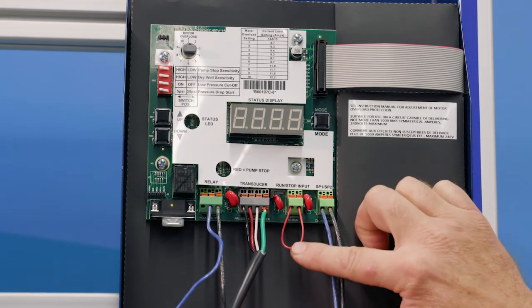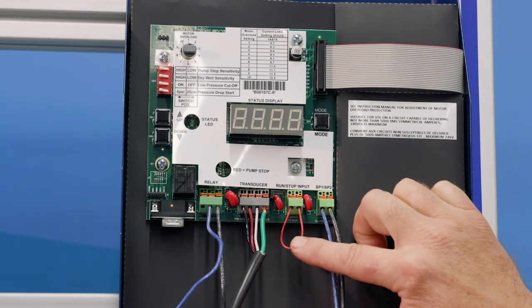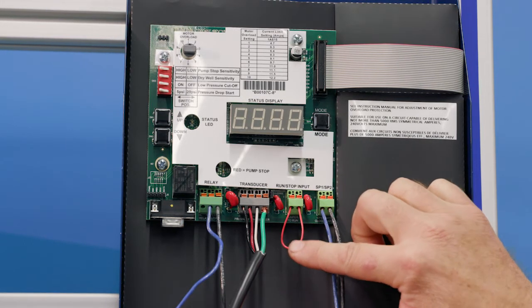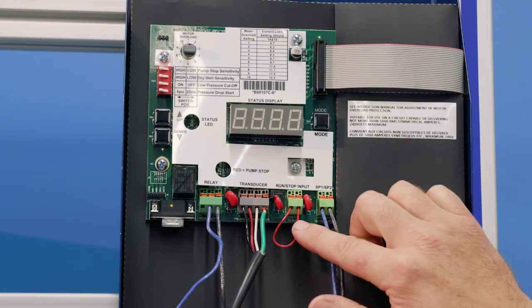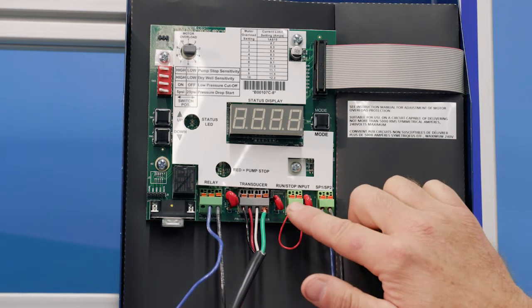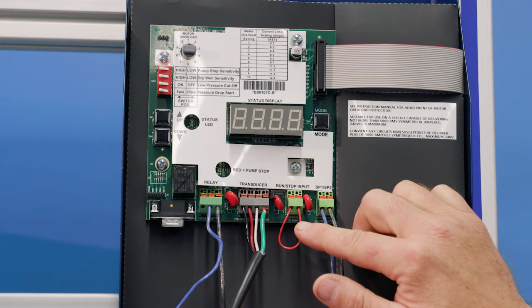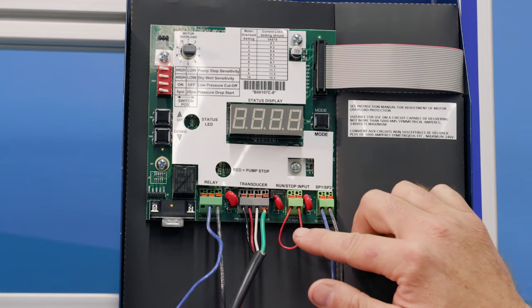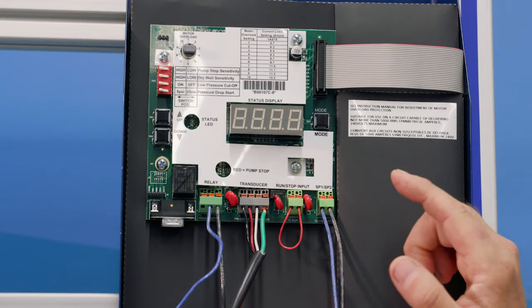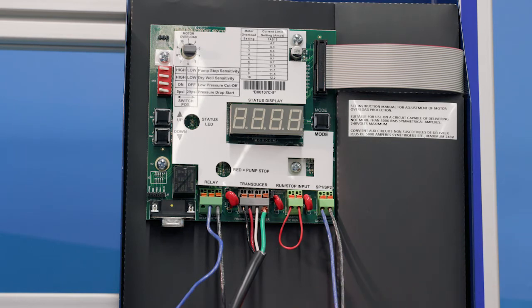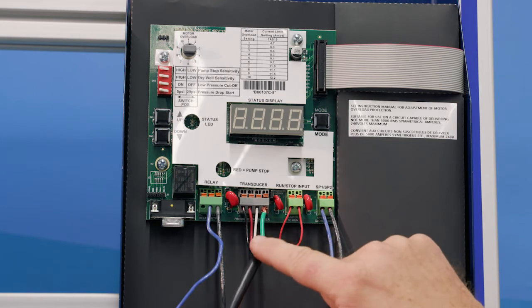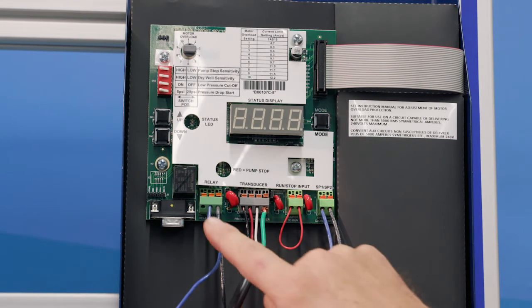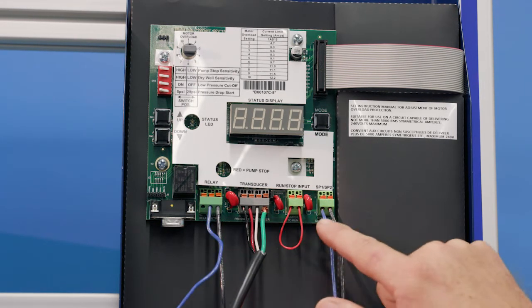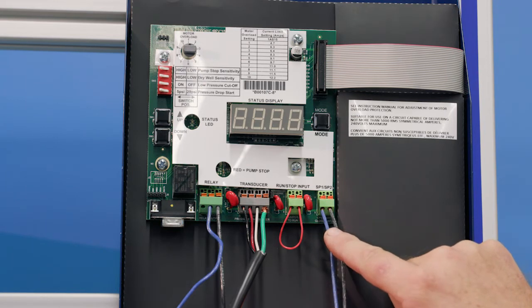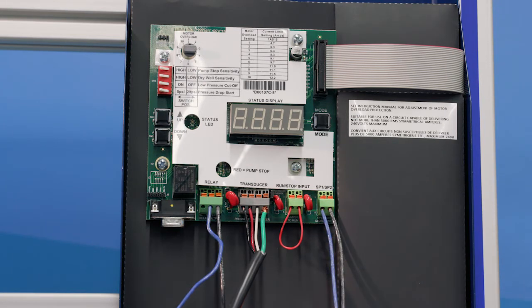The other wire here that does come with the box is a jumper. It's a run-stop jumper, indicating that when this is closed, this is going to allow the drive to run. If this is open, it's going to be off. So for this setup, we're just going to leave that jumper in, and then we're going to leave our transducer in. Our other wiring here is going back to the alternator, and so we'll talk about that next.